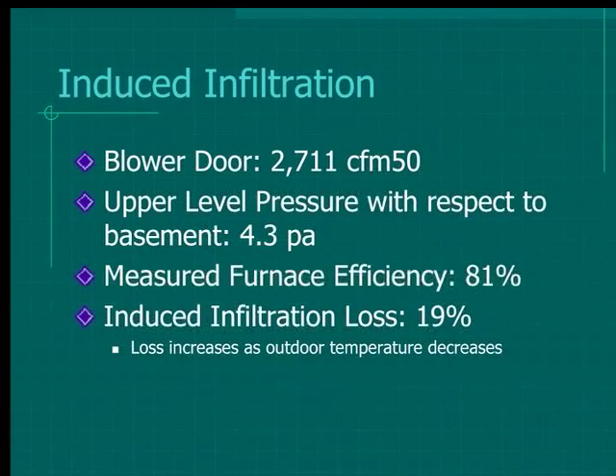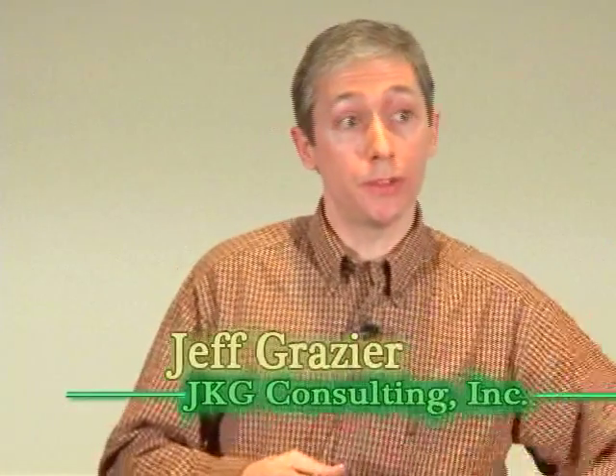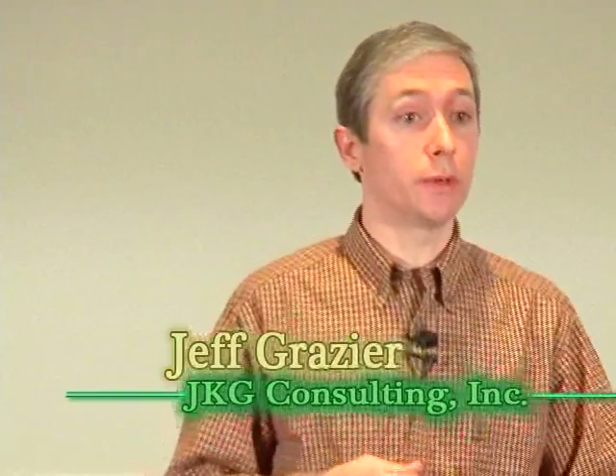This one's a little bit more technical. Actually, it has to do with that example I just talked about. Let's say on the efficiency audit, we measure your blower door number at 2711 CFM at 50 Pascal. We did a test on this house and turned the furnace on. So now get rid of the blower door; we're not thinking about that anymore. We just turned the furnace on. When we turned the furnace on, the upstairs was pressurized at 4.3 Pascal. The basement was depressurized at 4.3 Pascal.